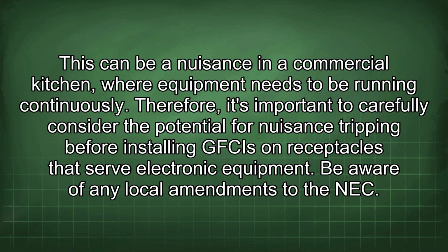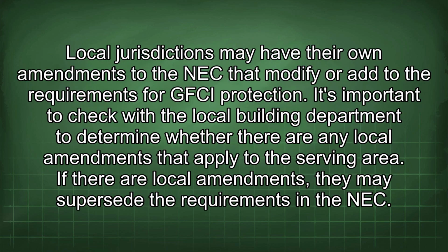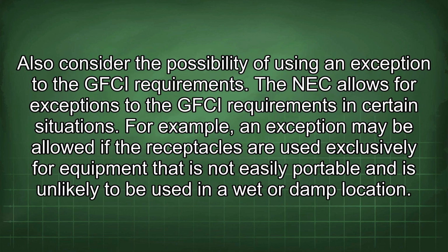Be aware of any local amendments to the NEC. Local jurisdictions may have their own amendments to the NEC that modify or add to the requirements for GFCI protection. It's important to check with the local building department to determine whether there are any local amendments that apply to the serving area. If there are local amendments, they may supersede the requirements in the NEC. Also consider the possibility of using an exception to the GFCI requirements. The NEC allows for exceptions to the GFCI requirements in certain situations.